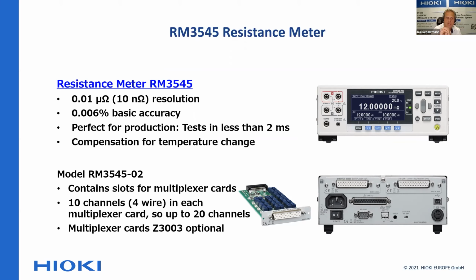You can see that because there is a model which allows you to add multiplexer units into that, which means you don't have only one tab weld measurement that you're going to do, but you can actually do that multiple times. And then you have a multiplexer unit and you can just switch through these. So you basically make one physical connection with multiple test pins, and then you just switch through each test point, make the measurement. This happens in less than 2 milliseconds. And this unit has multiplexers included.